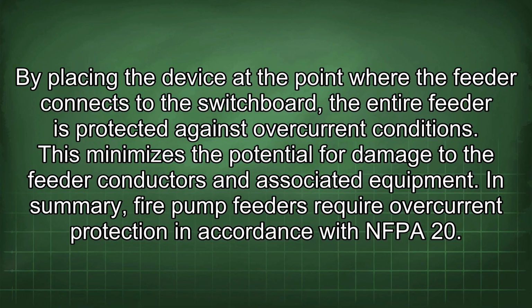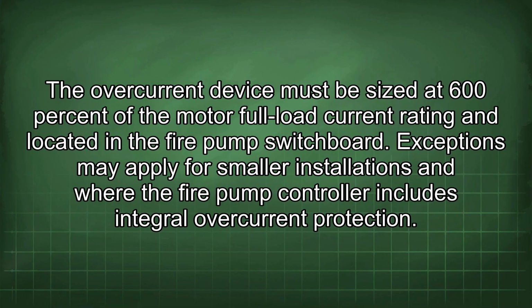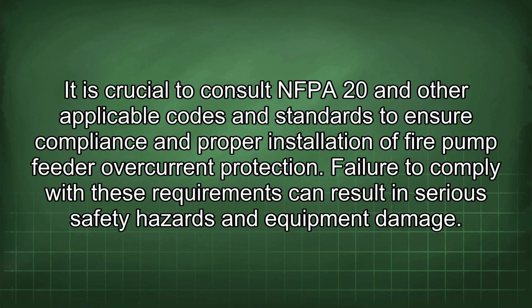In summary, fire pump feeders require overcurrent protection in accordance with NFPA 20. The overcurrent device must be sized at 600% of the motor full load current rating and located in a fire pump switchboard. Exceptions may apply for smaller installations and where the fire pump controller includes integral overcurrent protection. It is crucial to consult NFPA 20 and other applicable codes and standards to ensure compliance and proper installation of fire pump feeder overcurrent protection. Failure to comply with these requirements can result in serious safety hazards and equipment damage.